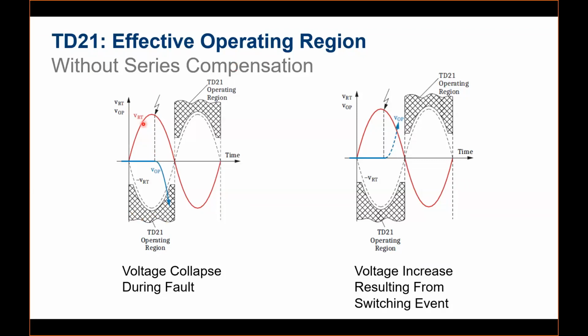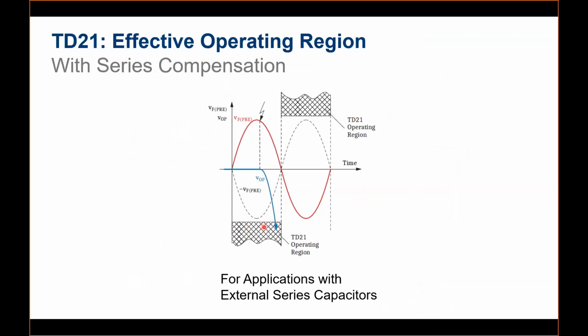It's just a concept where we are transforming the TD quantities into this plane. We have an operating region and a restraint region. In case of an internal fault, the voltage collapse, or the operating quantity, will enter your operating region. If you have another event, like a voltage increase due to switching or lightning, the operating quantity will go in the other direction, into the restraint region. So it's inherently secure. And we have added another security for series compensation. You can consider this as an operating region. For series compensated lines, we have this kind of characteristic, which is much more secure. We have trimmed that area and included it in the restraint region, where it was before in the operating region. This adds extra security for series compensated lines, whether the series compensation is inside the line or external to the line.